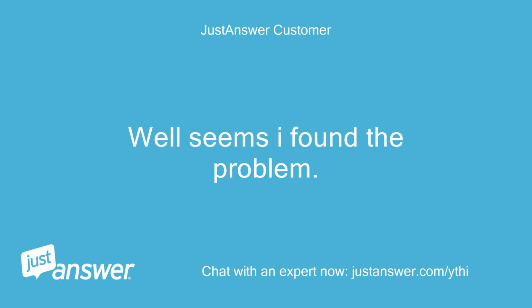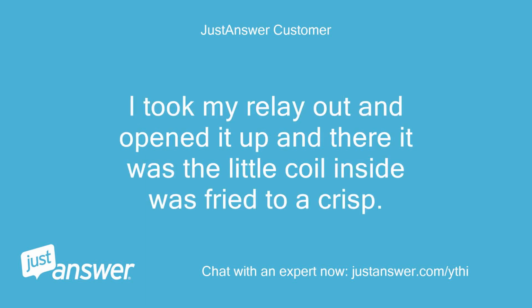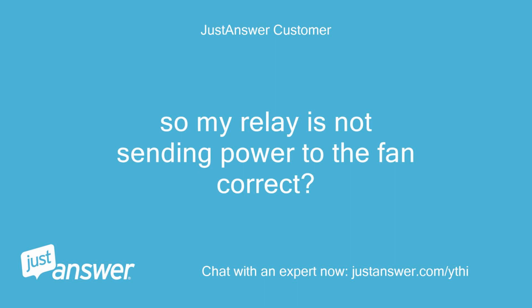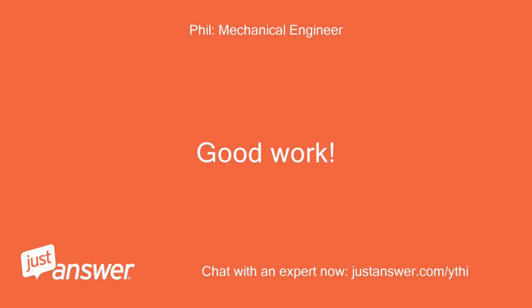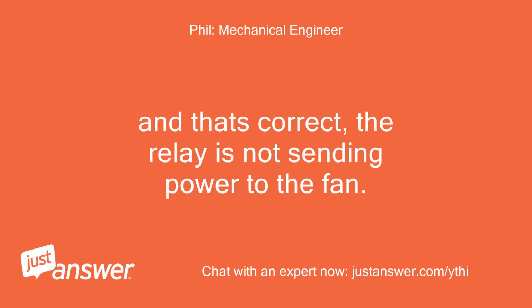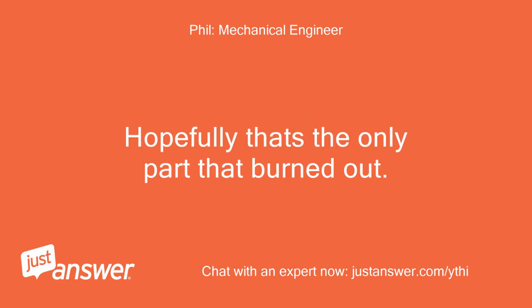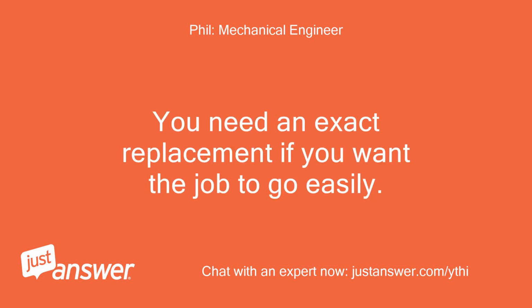Well, seems I found the problem. I took my relay out and opened it up, and there it was. The little coil inside was fried to a crisp. So my relay is not sending power to the fan, correct? Good work. And that's correct, the relay is not sending power to the fan. Hopefully that's the only part that burned out. You need an exact replacement if you want the job to go easily.